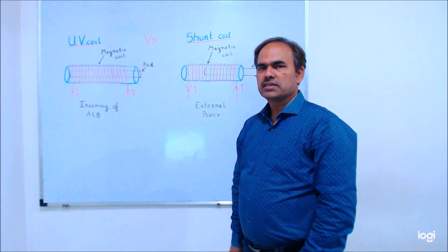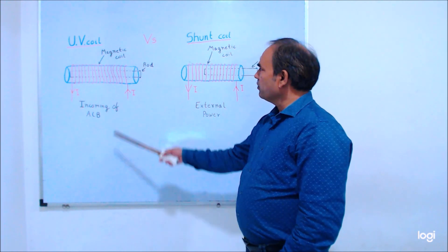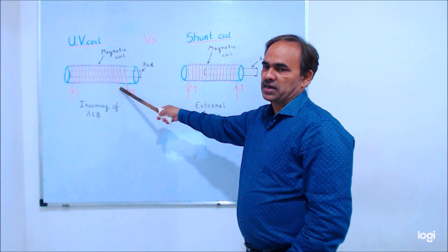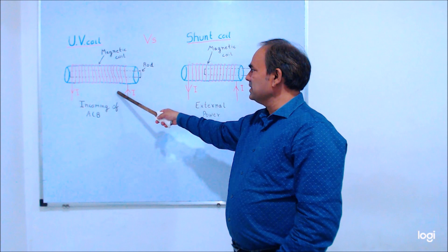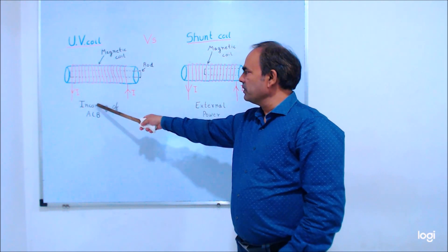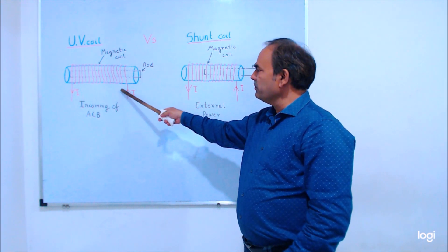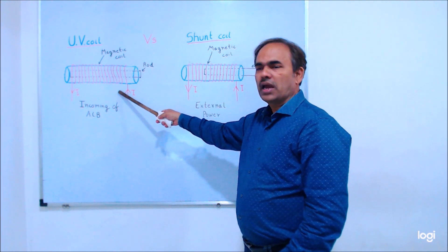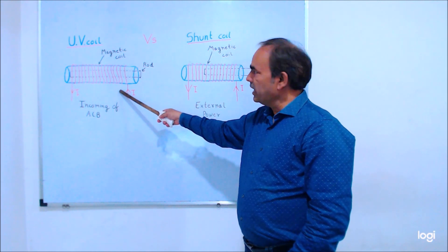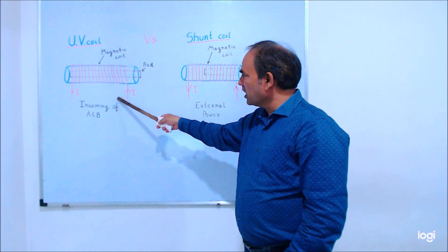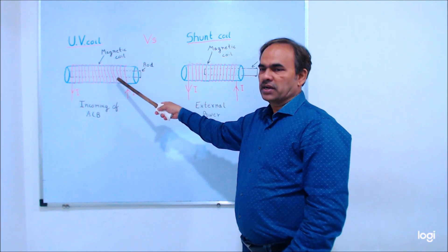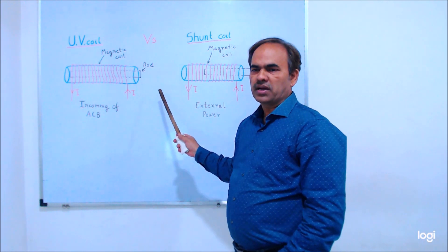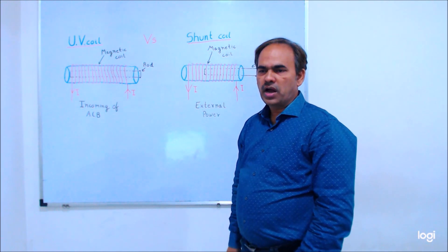One more difference: when the UV coil is de-energized — meaning the incoming supply is not available — we cannot close the circuit breaker. Similarly, when it is defective, we cannot close the circuit breaker. So it provides an interlock for the circuit breaker, acting as a safety feature.